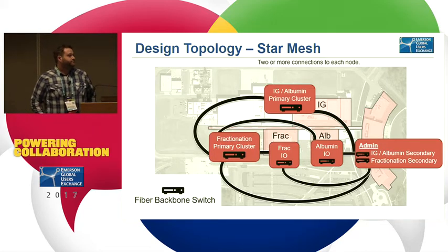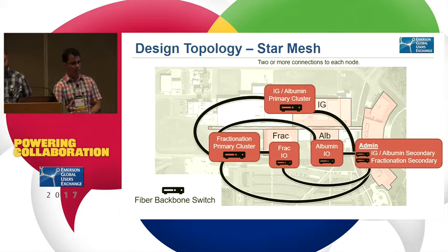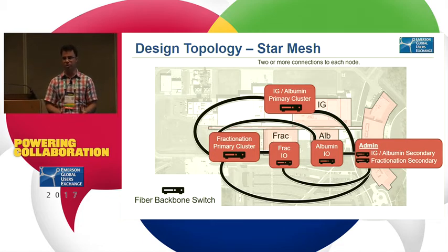One additional thing that is not in the presentation, but came to my mind now, is that we asked IT to provide us single mode fiber optic. Because if we chose multi-mode, then we would need to start with the exercise of measuring distances, and that's going to be huge. So we decided on single mode, so that we are sure we are designing for the distance that we need.